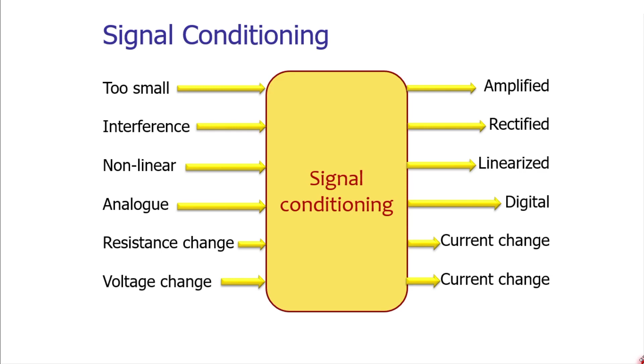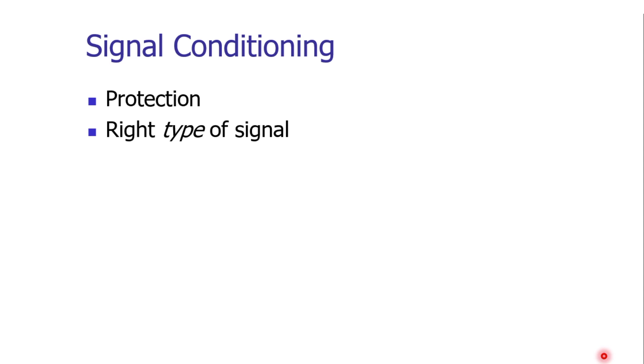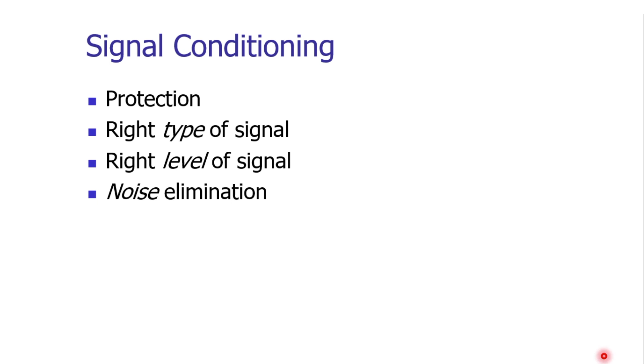To process the data which is coming from the sensor and make them into usable format is called signal conditioning. Thus, we can say that the signal conditioning has four basic functions. First is the protection function. The signal conditioning device should protect the microprocessor from undesired level of the signal. So we have to have the right type of signal with right level of magnitude without the noise or the interference. So protection from harmful level of signals, harmful types of signals, and elimination of the interference or the noise.